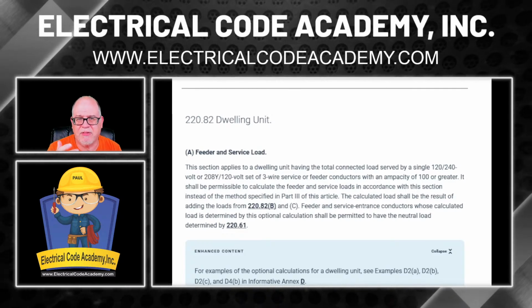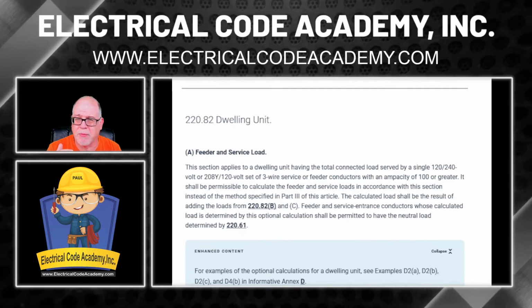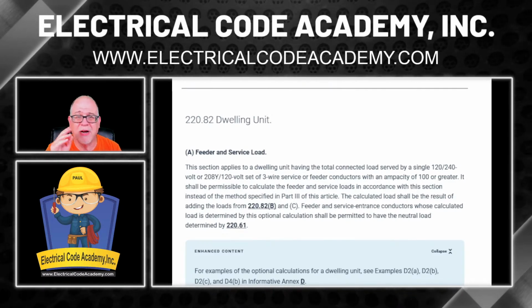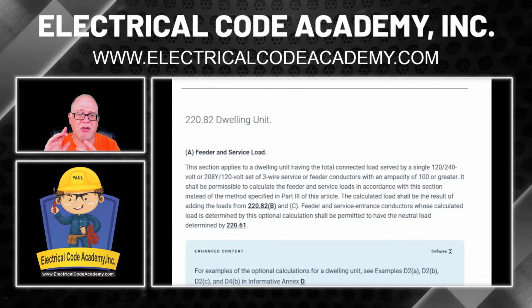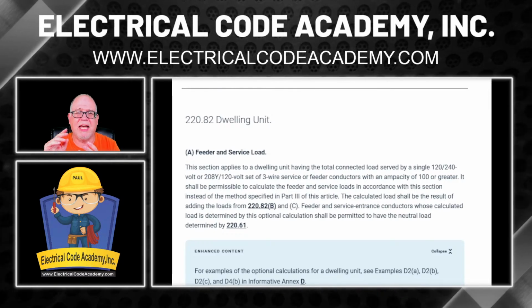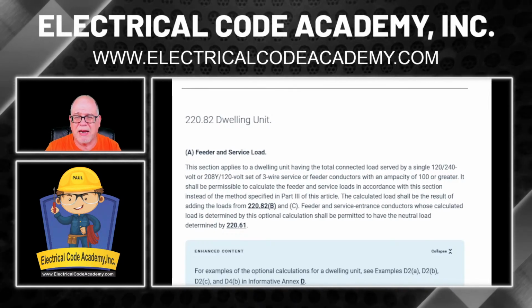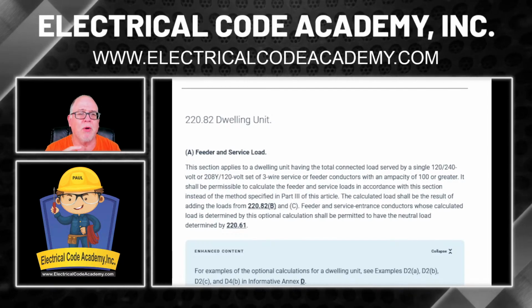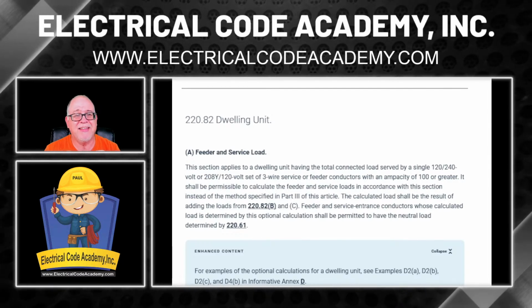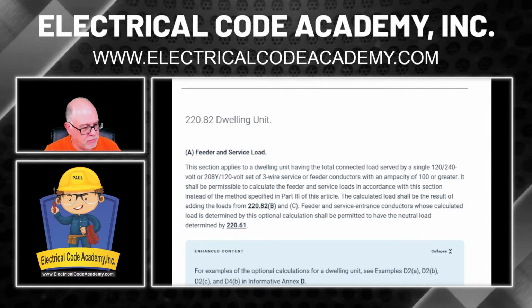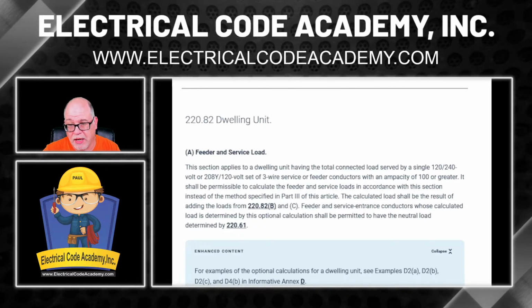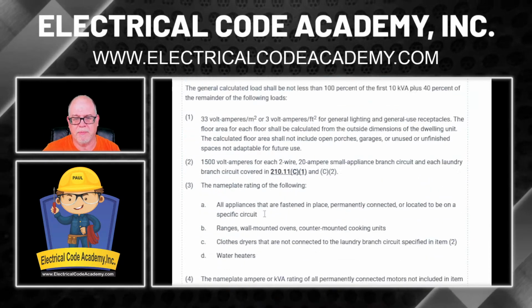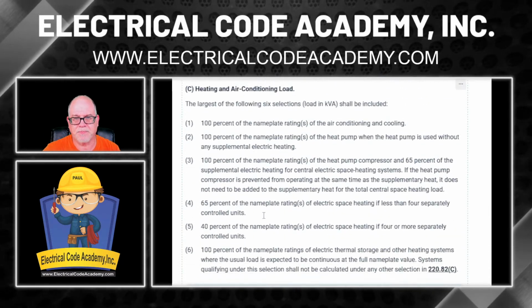B is the one that deals with the 3 VA per square foot, and talks about adding up all the nameplates, the first 10,000 at 100% and the remainder at 40%. We're not even doing any of that because we're not even looking at cooking. We're not even looking at appliances. We're not even looking at 3 VA per square foot. All we're being asked to do is deal with the heating and air conditioning, right? So we want to move on down to what we're working with in our question, and that is right here.